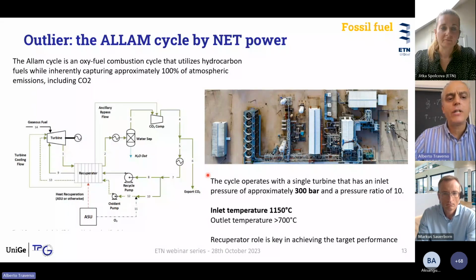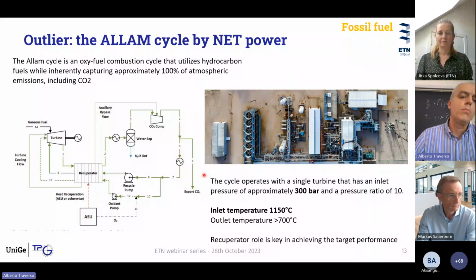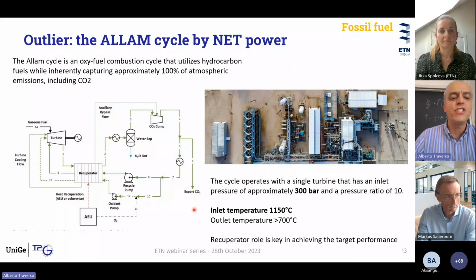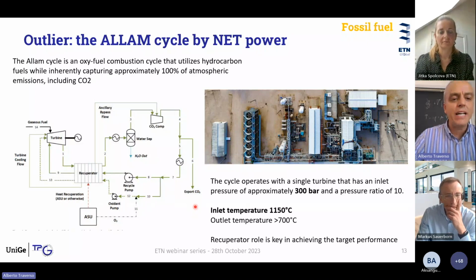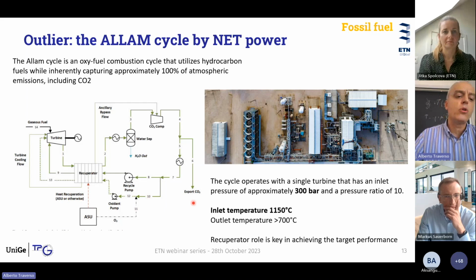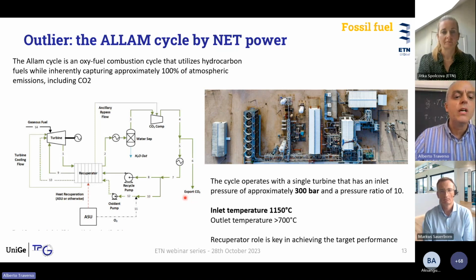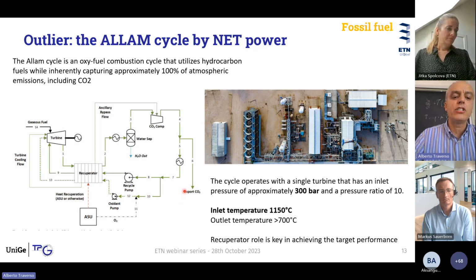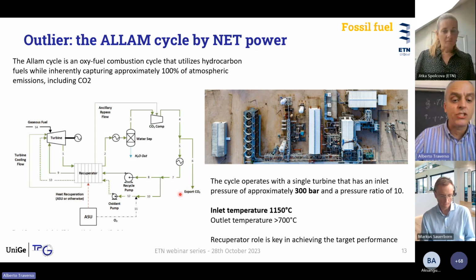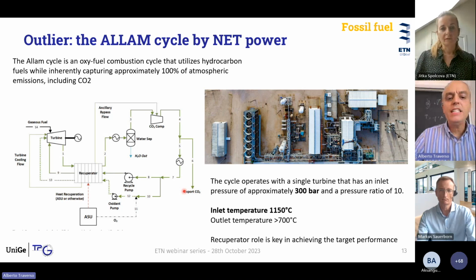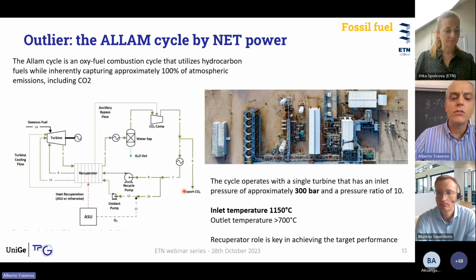I said I wanted to mention the outlier turbine. This is the only oxy-combustion case I mentioned, but for this cycle, also called the Net Power cycle or Allam cycle, the conditions to operate the turbine are particularly demanding. In fact, the system targets power production from fossil fuel with parallel CO2 separation and export at pressure to some reservoir. And in this case, we see that the design condition for the turbine is 300 bar with an expansion ratio of about 10.